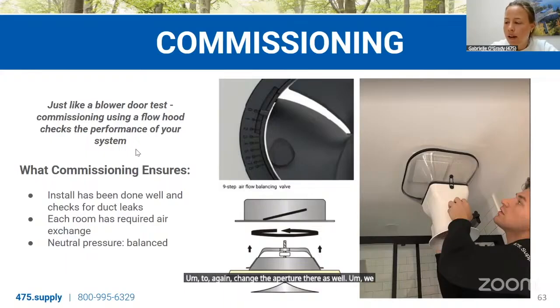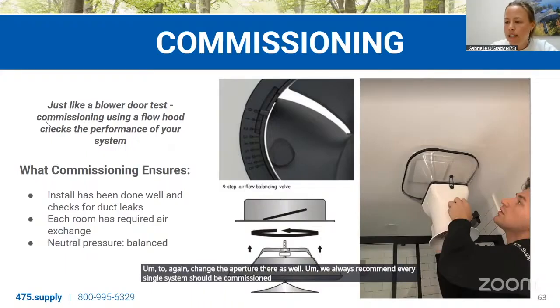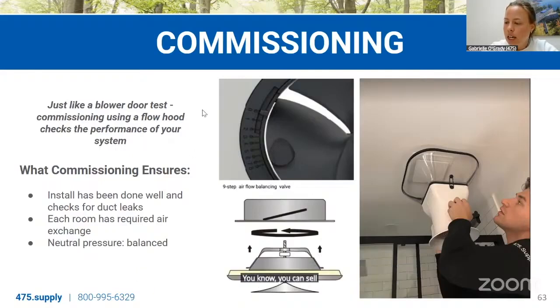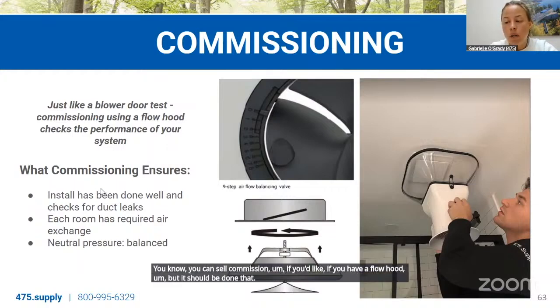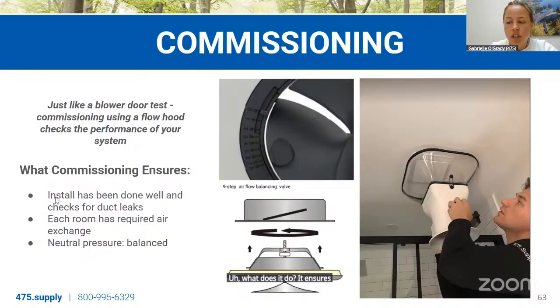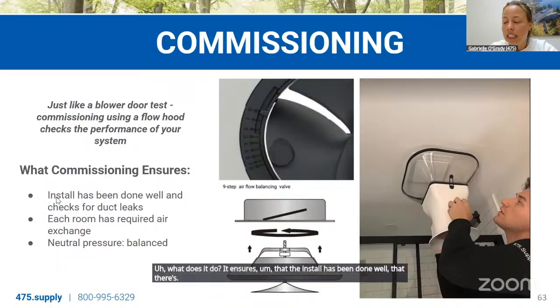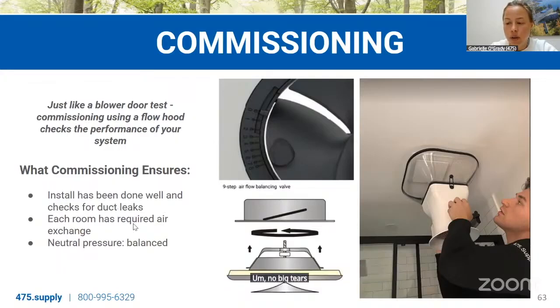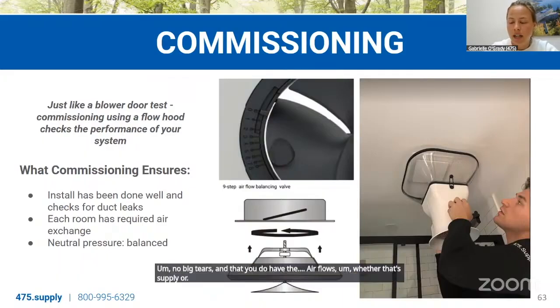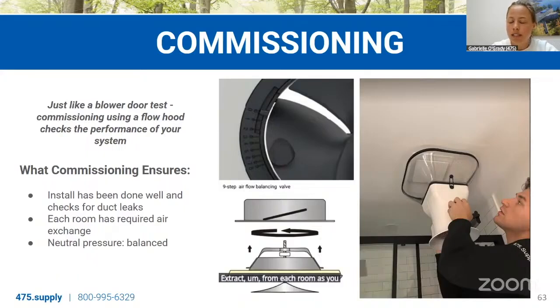We always recommend every single system should be commissioned. We don't mandate it; you can self-commission if you'd like, if you have a flow hood, but it should be done. What does it do? It ensures that the install has been done well, that there are no duct leaks, no big tears, and that you do have the airflows, whether that's supply or extract, from each room as you planned, as was designed. So just like we recommend a blower door test for testing how airtight a building is, using a flow hood and doing the commissioning is the way to check if the system's working.